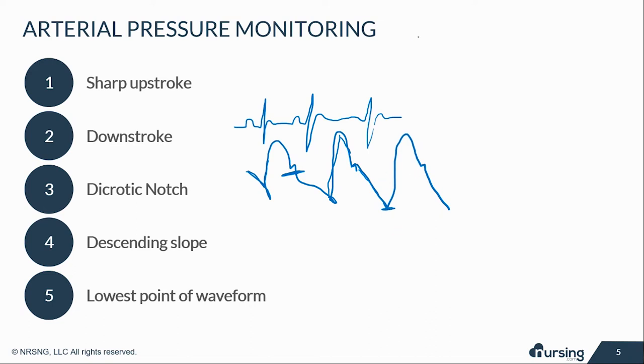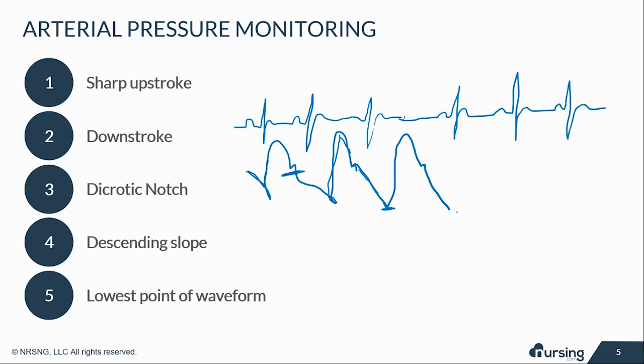This is how your A-line waveform should look, and it should correlate with your EKG — the waveform will come just after the QRS complex.